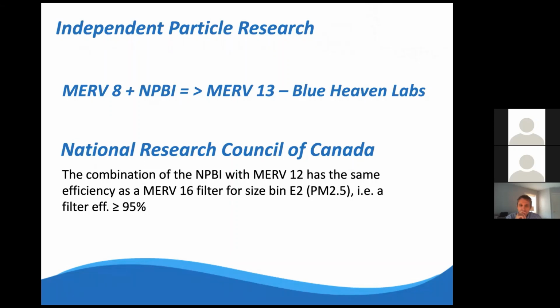But the problem is if you go from a MERV 8 to a MERV 13 and that pressure drop goes up because of the filter media being more dense, if your supply airflow actually goes down because the fan cannot handle the additional static pressure drop, your total particle counts are likely to go up in the space. So even though you have a more efficient filter, particle counts can go up in the space if the airflow goes down, which impacts the total air exchange of the space.